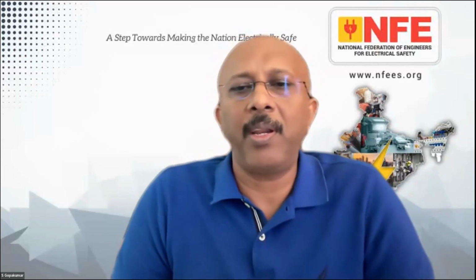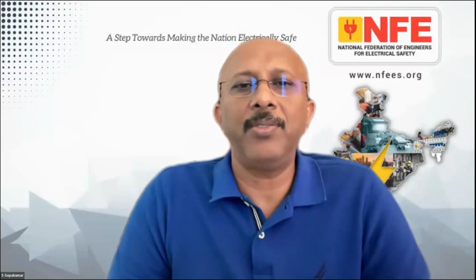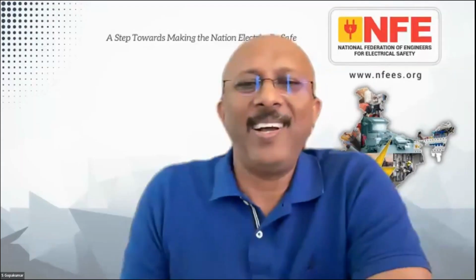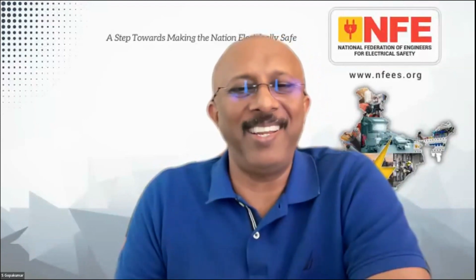And now, Mr. Peter, will you be able to address this? Okay, well, pretty much I'm thinking right now, as the regulation says that we need to test it for all sources. Well, definitely the one for the transformer, but in case the transformer fails and we're going to use a diesel generator, okay, it might also be a good idea. I'm thinking right now about this because it's all connected with the regulations here. I would explain my experience, of course.